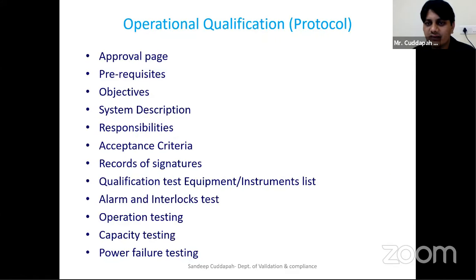Then the operational qualification protocol has the same structure as installation qualification. The only difference is that in operational qualification you will be doing alarm and interlock tests, operational testing, capacity testing, and power failure testing. In installation qualification, you need not switch on the equipment at all. You will see whether the components are present or not. But in operational qualification, you will verify whether the components are working or not.